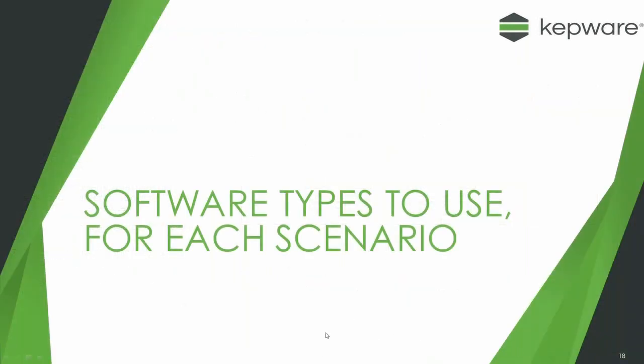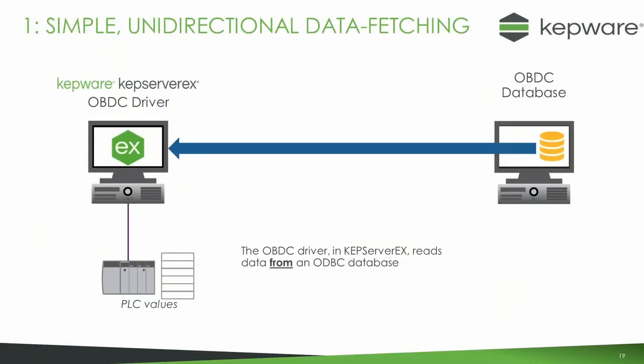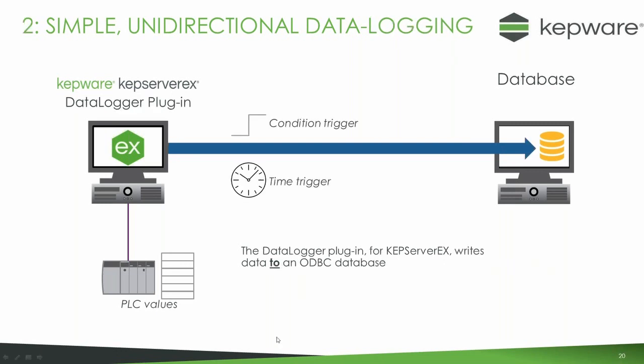So how do you solve these particular problems? For the unidirectional data fetching scenario, this is simply the ODBC driver inside KEPServer, used for reading data from an ODBC database — a one-way driver from the database down to the PLC. For the data logging scenario with time triggers or conditional triggers — data being sent from the PLC to a database — that's achieved using the KEPServer plugin called the Data Logger, which is actually the most common plugin we provide to KEPServer users.